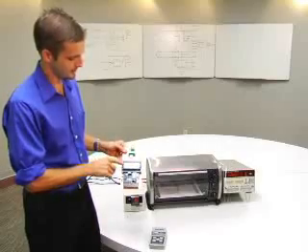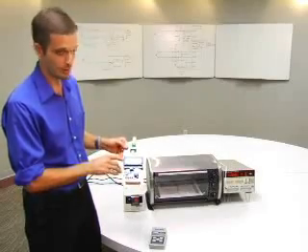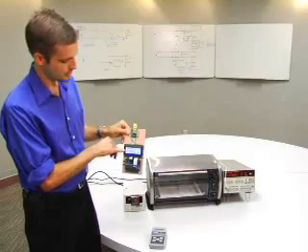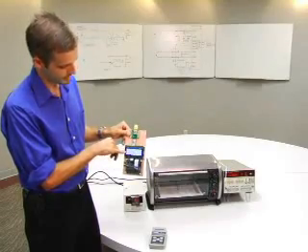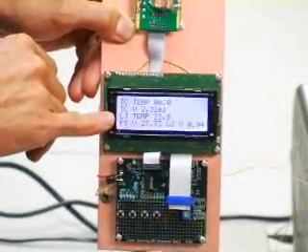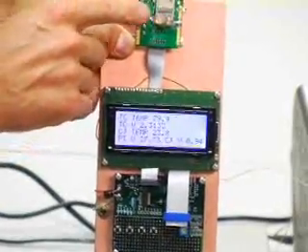Some other information, and this will help with understanding how these meters work a little bit better. We've also got the thermocouple voltage, which at 80 degrees centigrade is about 2.3 millivolts. The cold junction temperature is about 23.8 degrees centigrade, which is the temperature of the internal temperature sensor.